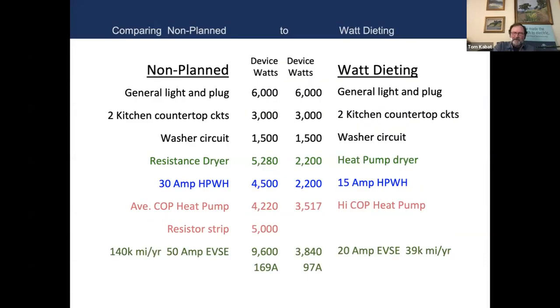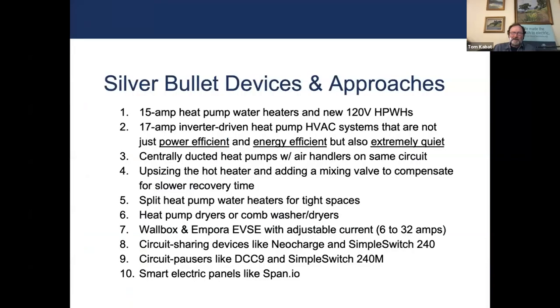Anyway, that's just another example of planned and not planned. So my partner, Josie Gaylord, and I did a study for San Mateo County, and we found a number of kind of silver bullet devices that really helped us stay on the existing 100 amp panels. Those were the 15 amp water heaters and the new 120 volt water heaters, and these super efficient heat pump space heaters, which were only 17 amps for an inverter-driven 3-ton heat pump. Also, upsizing the water heater tank and adding a mixing valve to compensate for the slower recovery time gave people lots of hot water during hot water rush hour and let their water heater reheat while electricity was cheap across the middle of the day.